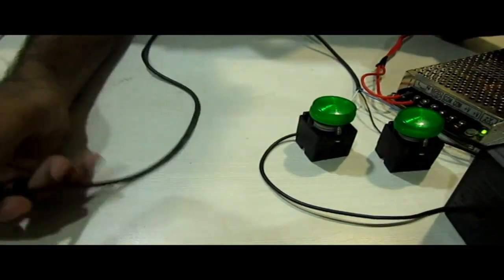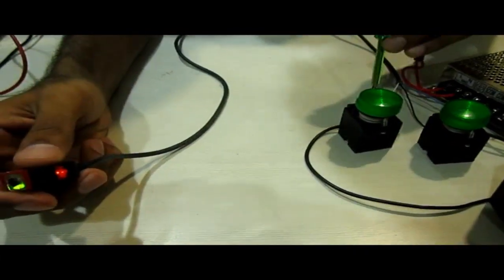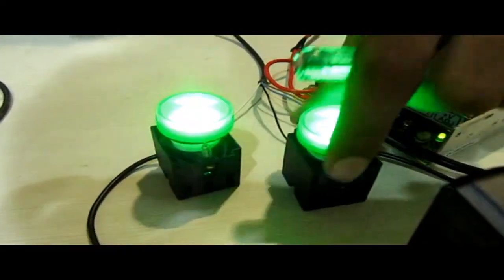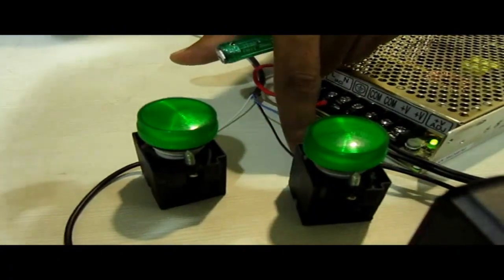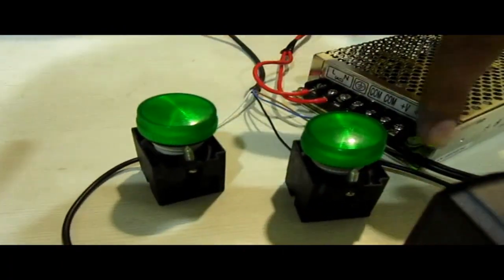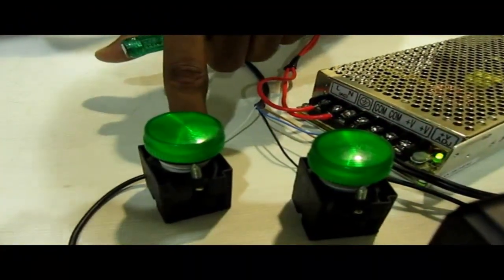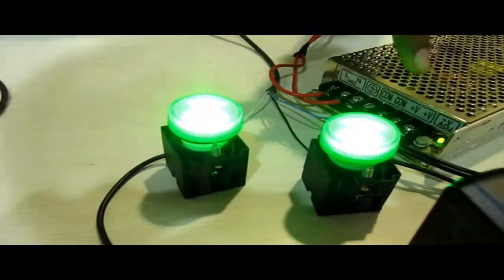Now you can see here I have connected the output wires of the sensor to the indicators. The black wire is connected to this indicator. From this we are getting 24 voltage and 0 voltage is provided from the power supply. In this indicator the white wire is connected which is giving 0 volt and the 24 volt is provided from the power supply.